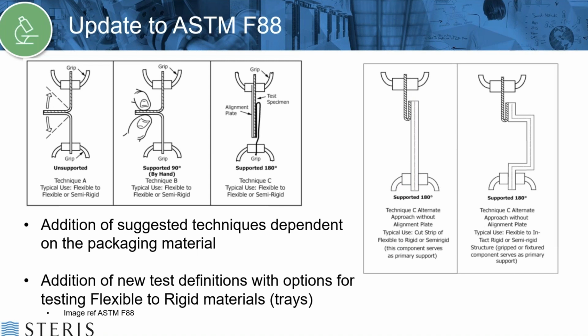So ASTM F88 is the peel test standard, and there's been some recent updates to that. There was an addition to allow for flexible to rigid material, so like a thermoform tray. Most people were using the standard for that type of testing previously, but the standard didn't specifically call it out. It now does. The other addition is suggested techniques depending on the packaging material. These pictures here are straight out of the standard. You can see underneath where it talks about the typical use. So flexible to flexible or flexible to semi-rigid. Again, talking about the different types of packaging that would make sense to use for the different types of test methods here.